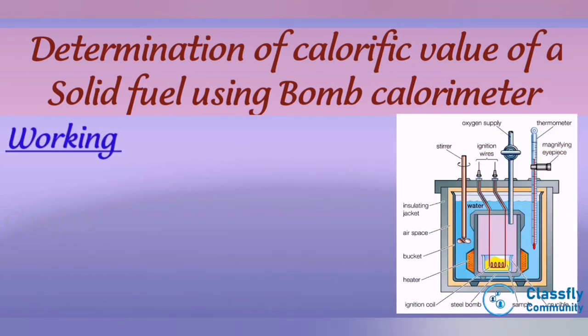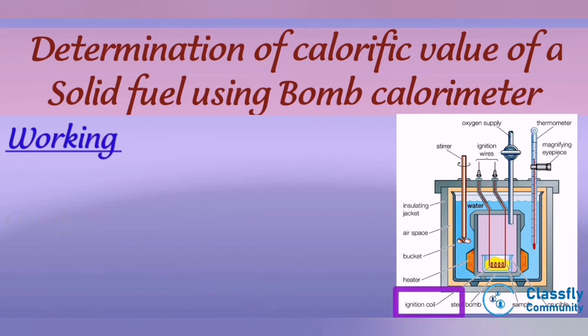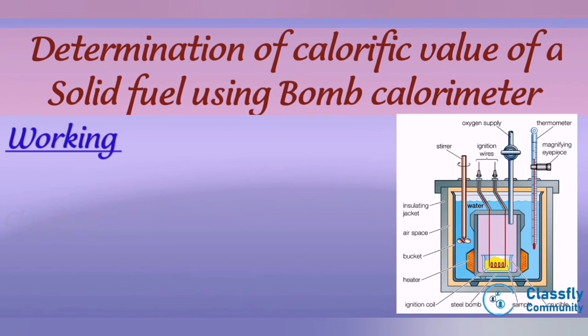Working: a known mass of solid fuel is placed in a crucible. The crucible is placed inside the bomb, and the lid is closed tightly. The bomb is placed inside the copper calorimeter with a known mass of water. The bomb is filled with oxygen at a pressure of 25 to 30 atmospheres. The initial temperature T1 is noted on the thermometer. On passing an electric current through the ignition coil, the fuel gets ignited and burns, liberating heat. The water is continuously stirred using the stirrer, and the maximum temperature attained by the water, T2, is noted.